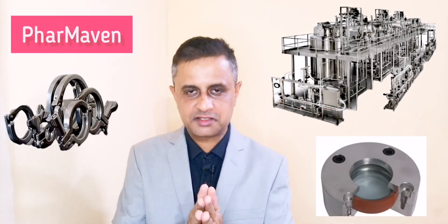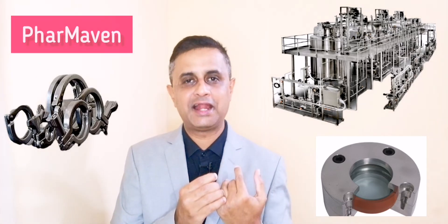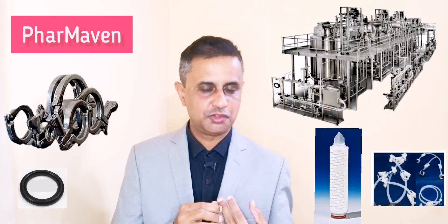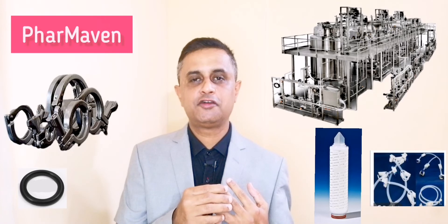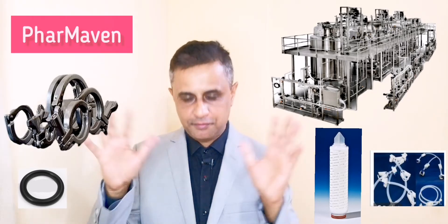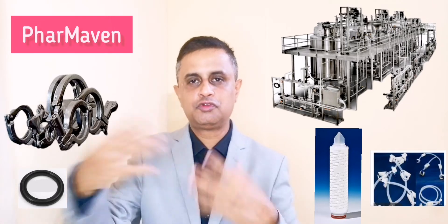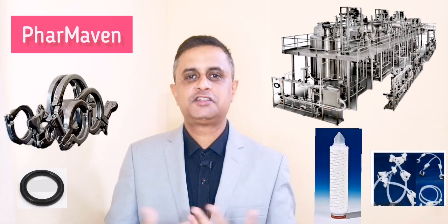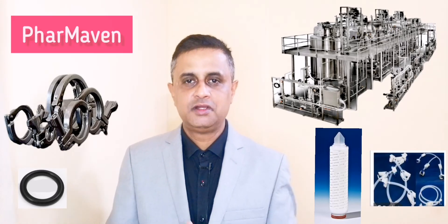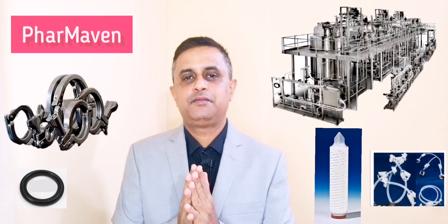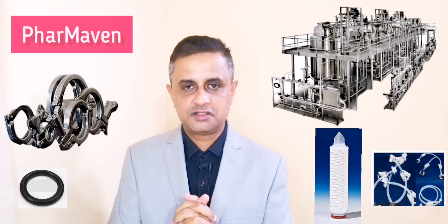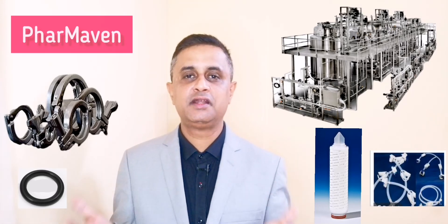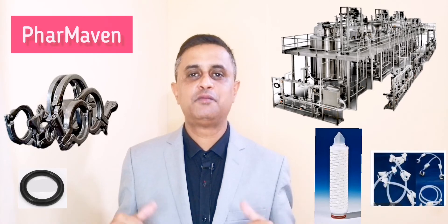Ensure that you have proper connections, proper gaskets, and all connections are checked. There should be no dead legs and no areas where proper steam penetration is not achieved — including your filters, connections, vent filters, connections to the filling line, and all drain points of your system. Ensure that each and every part of your system is reaching the required temperature. Only then proceed with the media fill. This is how to avoid media fill failure in a complex multi-vessel system.